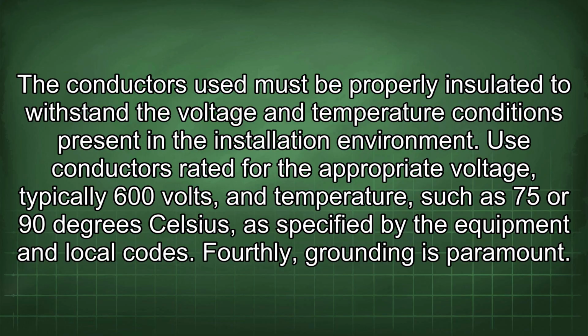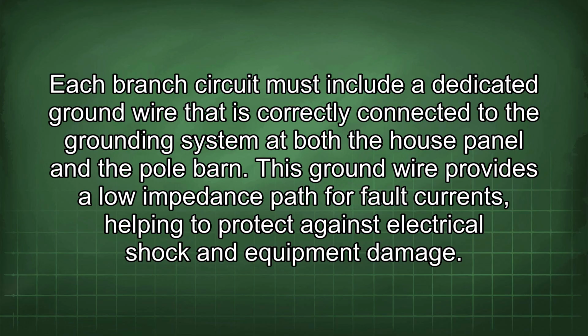Fourthly, grounding is paramount. Each branch circuit must include a dedicated ground wire that is correctly connected to the grounding system at both the house panel and the pole barn. This ground wire provides a low impedance path for fault currents, helping to protect against electrical shock and equipment damage.